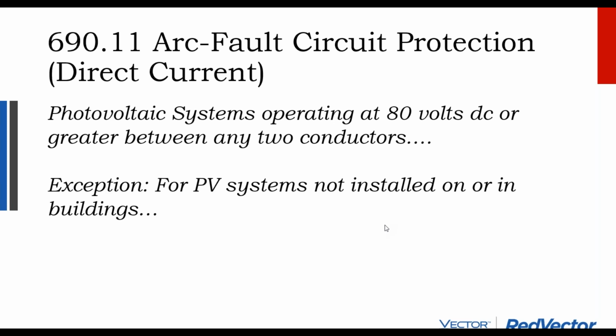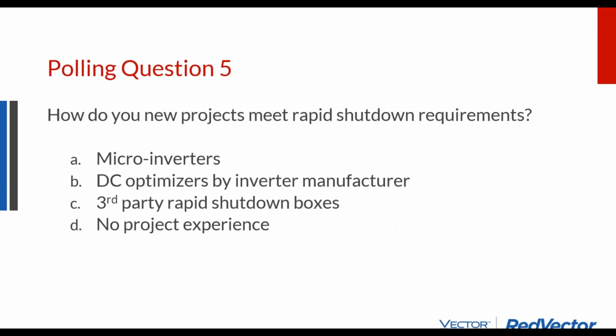So if you imagine you have a power cable and you slowly pull it apart and you get a little spark between the two cables, that's an arc fault. Whereas a ground fault is you take the power cable and you connect it to a piece of metal that's connected to ground, and you're draining all the power in the cable into the ground. So in the past, solar hasn't had arc fault requirements, and solar has had this reputation for having nothing ever go wrong with it. All of a sudden, we get arc fault detection into our solar inverters, and there's a lot more tripping going on due to bad workmanship. Things like mismade connectors, they're not necessarily touching ground, but if your connector is not well seated, you'll get arc faulting across the connector. So that's detected nowadays.